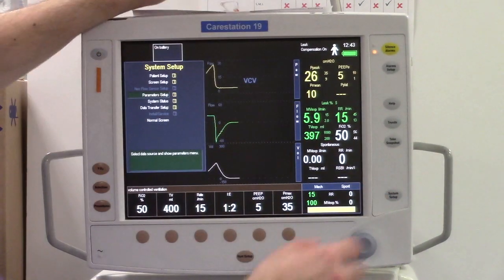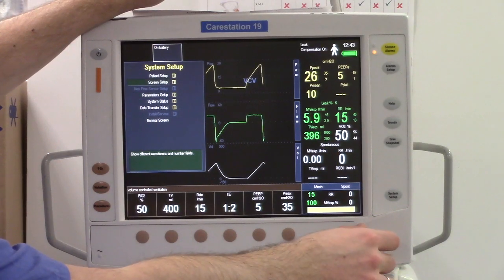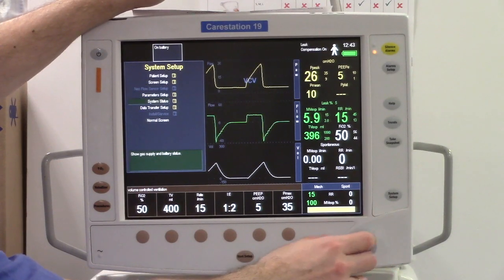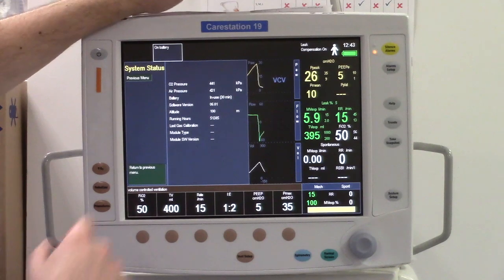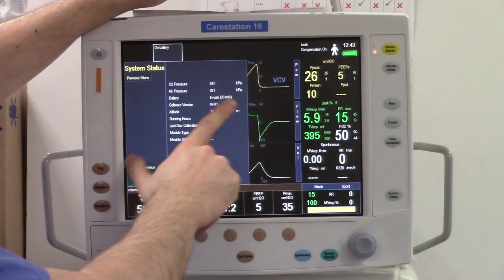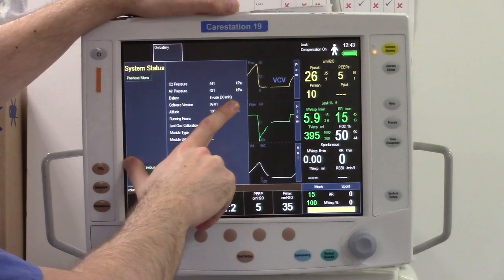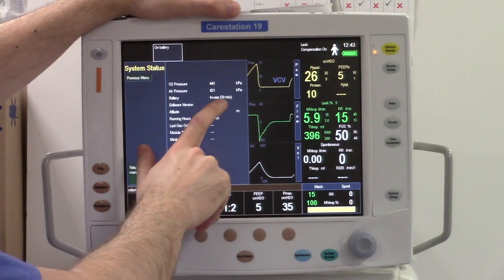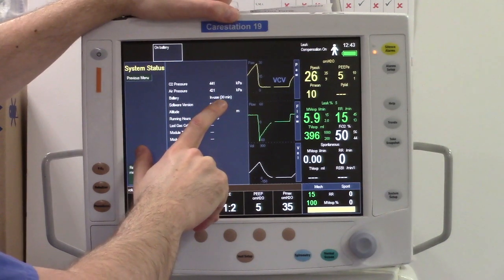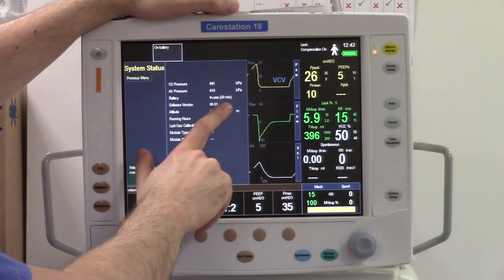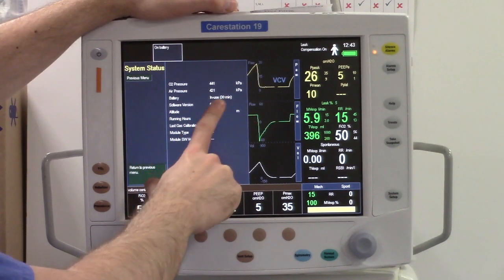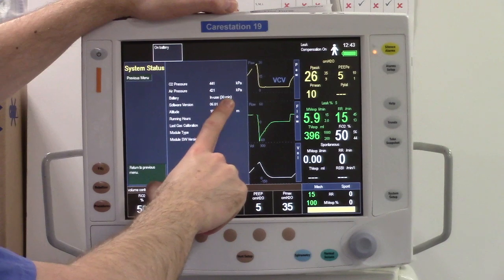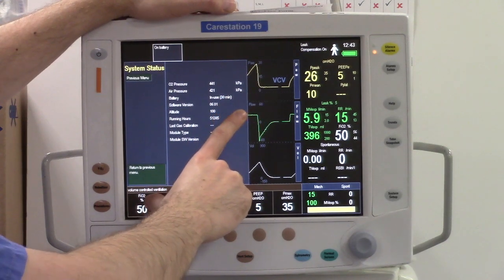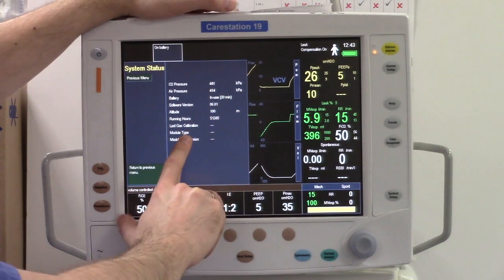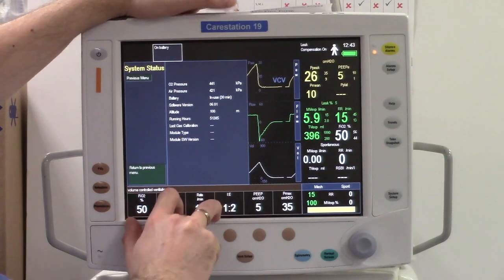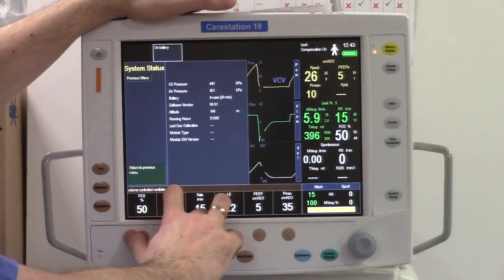Okay, going through the next one, system status. So when you select this, it will usually tell you how much battery is left. Yeah, it will show you the maximum. It will always show you 30 minutes. Yeah, when you go below 30 minutes, you'll get an alarm saying less than 30 minutes. Then you get another alarm when it's less than 20 minutes, another alarm when it's less than 10 minutes, another alarm at less than 5 minutes. Yeah.